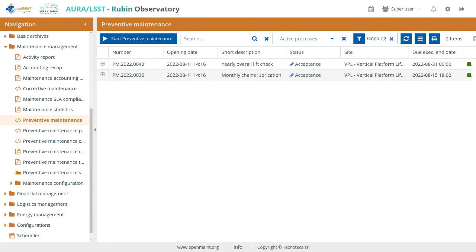But I understand you're looking for a more automatized approach to get information from sensor values and things like this. And it's actually possible. This goes on the software interfaces that are here. Maybe, Alberto, if you have a bit on this one, you could explain. Yes, of course, we can, for example, start not only maintenance activities based on a schedule, but also based on, maybe, 2,000 working hours, or there is an alarm. So based on events, hours of usage, or alarms or notification that the pressure is too high, start the maintenance based on that, or also on statistics or collection of data put together that indicate the need to start the maintenance. So we can do that.